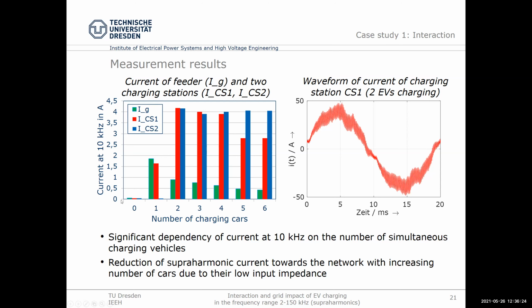If we connect one car, the emission is more or less similar - there's a slight difference which could be caused by measurement uncertainty, but it's more or less the same. What you should look at is that we're talking about 1.6 amps - we don't mean milliamps, but 1.6 amps at 10 kilohertz flowing into the network just because one EV has been connected.